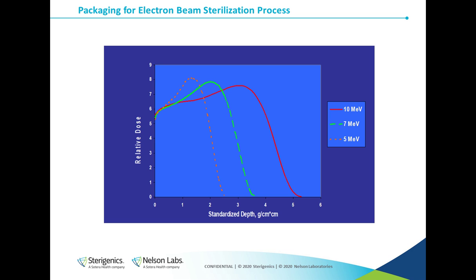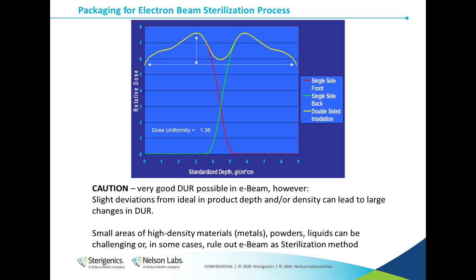On this slide, you can see the different depth dose curves of various energy electron beams. Typically, we use 10 MeV electrons for the radiation sterilization process, as anything lower would not be very useful for many products due to the reduced penetration at lower energies. And anything higher than 12 MeV has the potential to induce radioactivity into the product.